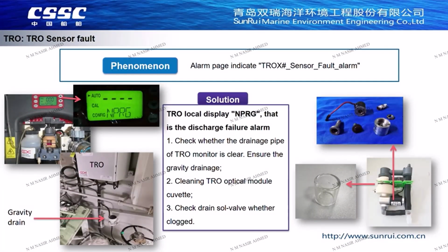The second TRO fault alarm is caused by the TRO sampling water discharge fault. TRO will display the NPRG alarm code locally to notify of drain failure. First, check whether the TRO discharge pipe is gravity installed. It should be discharged directly into a funnel or similar container. Also, the drain pipe from the TRO box should not be too long.